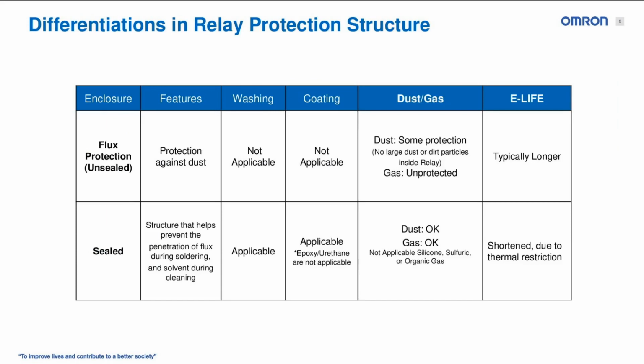So what are the differentiations between the relay protection structures according to Omron? We're looking at the enclosures here on the left. We call them flux protected type, which are unsealed type, but protect against flux and dust. And we also have the sealed type below that. So first, for flux protected, it protects against dust getting within the relay and causing any issues with the contacts or contact resistance change. These relays are not fully sealed, so they cannot be washed or coated. It has some protection against dust, but it is unprotected against gas.